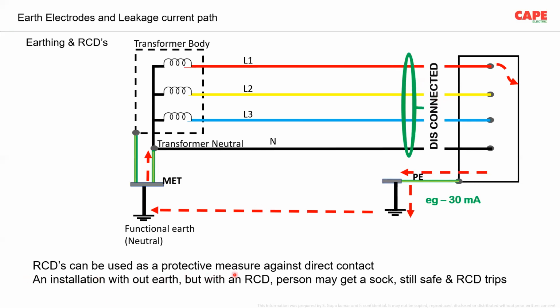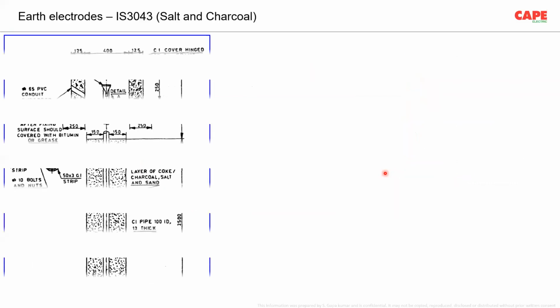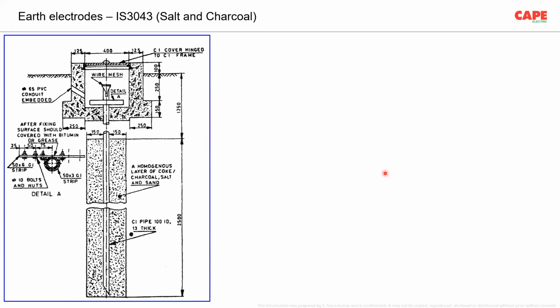RCDs can be used as a protective measure against direct contact. Direct contact means, even if somebody touches the live part, let us say where I am scrolling, then immediately the RCCB trips. Whereas with an ELCB, it is not the case. So the use of the ELCB and earth electrode was very much important during olden days, especially before the introduction of RCCBs. After the introduction of RCCB, of course, earthing and protective equipotential bonding are very much necessary, mandatory.